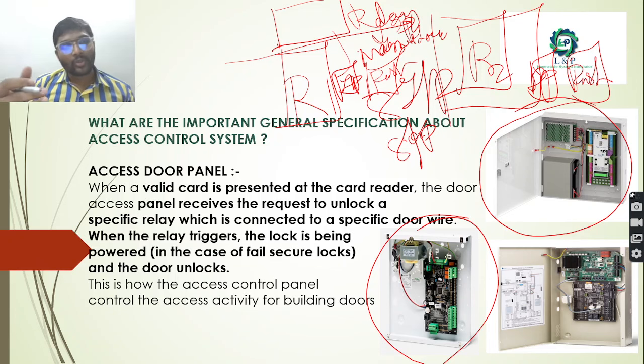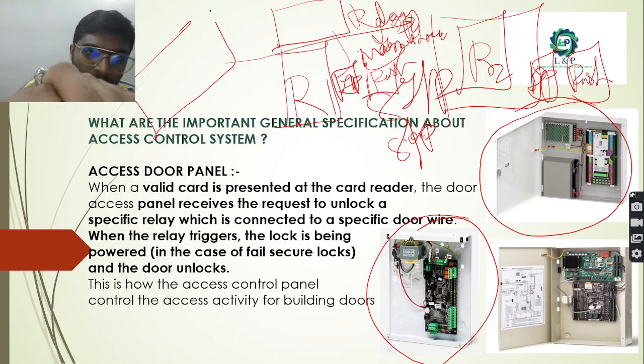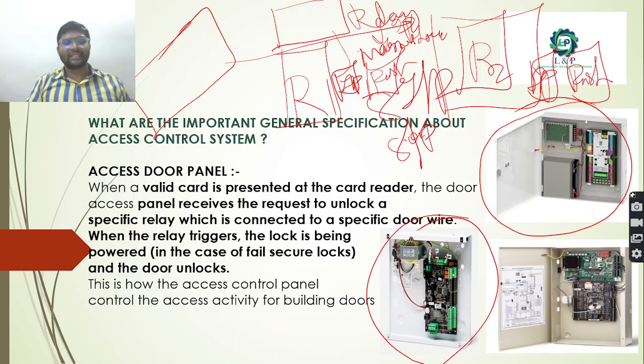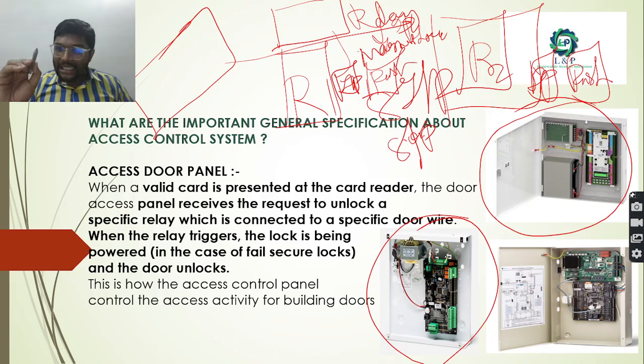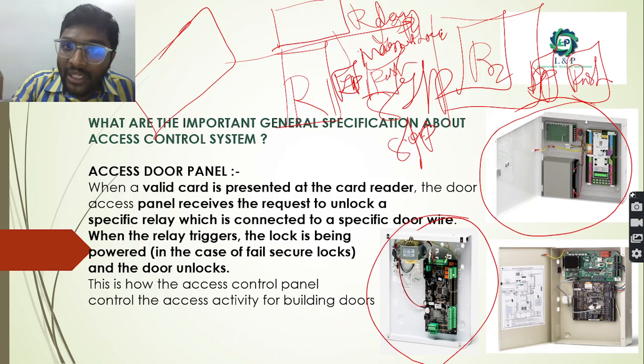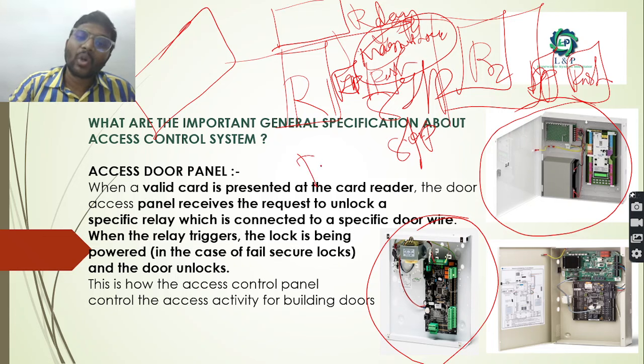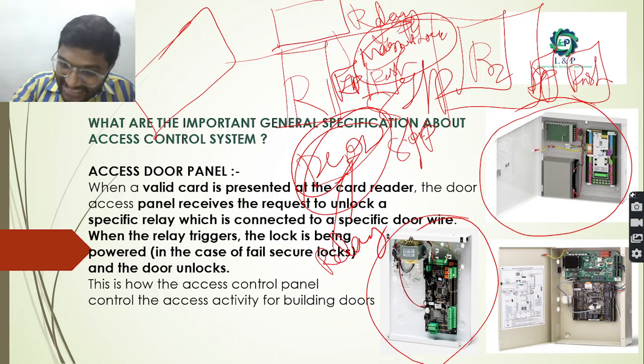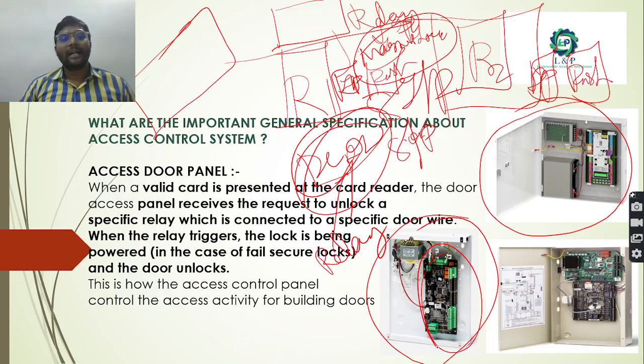When a valid card is presented near the card reader, it is the duty of the access control panel to receive the request and unlock the specific door. To magnetize or demagnetize the magnetic locks, we need the help of relays, which are present inside the access door panels.